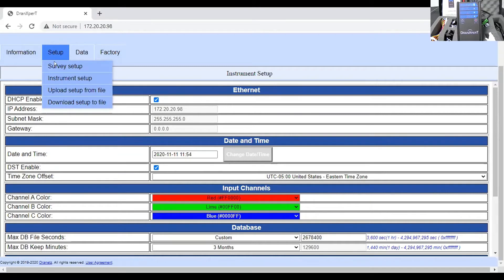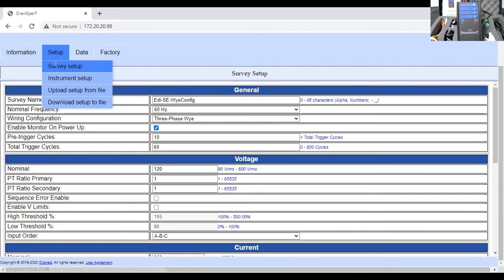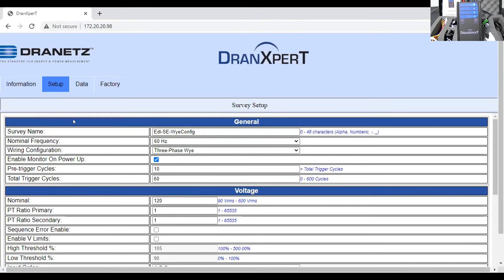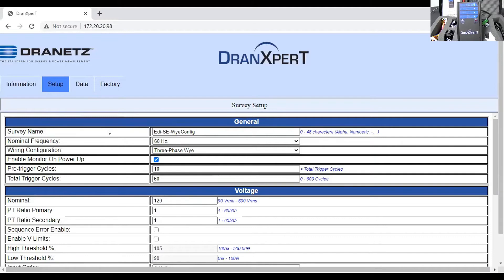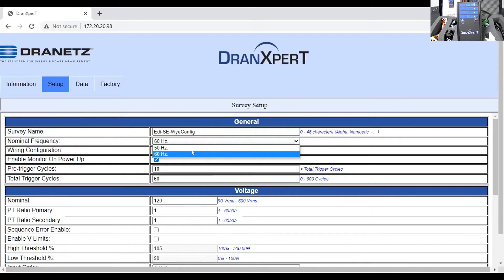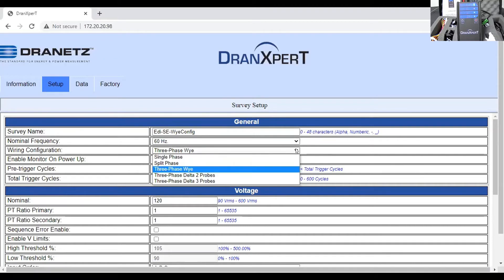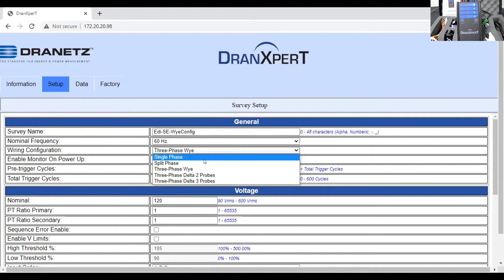The next step is what we call the survey setup. This is where you really get into the meat of setting up the instrument. A lot of it is very intuitive. For example, the survey name. As I mentioned earlier, it's always recommended that you give the survey a name. Another way you can think of a survey is a monitoring session. You want to give it a name that allows you to better organize the data when you're doing it in post. And then you have things such as the frequency. Obviously, we can support frequencies other than 60 Hz. You can see the drop-down for 60 Hz. Circuit types. The drop-down for circuit types. You can see the various circuit types that we support. And by the way, these are the most common circuit types that you're going to encounter. Your deltas, your y's, whether it's delta 2 probe or delta 3 probe.